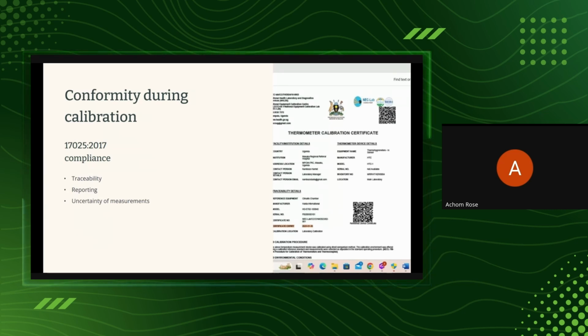You have to have a report which shows all the aspects listed within the 17025. You have to show the title, and who is calibrating. On the right side is just a sample of our certificate: the details of the equipment, the traceability details, and the results. Within the results, we have to give the uncertainty of measurement. The uncertainty of measurement defines what we call calibration. If you don't have uncertainty of measurement, then all we are doing is a verification.